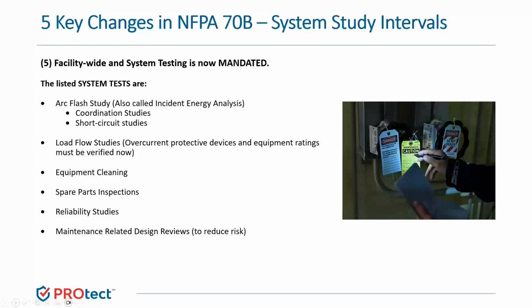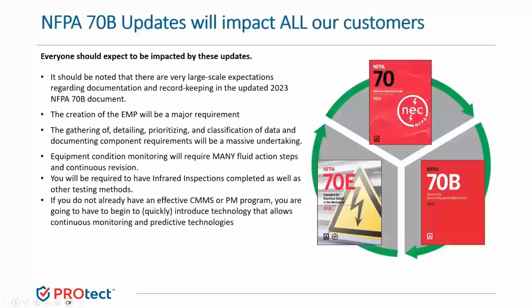A big key takeaway here is that if you already have an effective CMMS or preventive maintenance program, you should be able to build an electrical maintenance program that you can easily integrate with your existing mechanical integrity programs. You'll just need to pay close attention to manufacturer recommendations and defer to those NFPA guidelines on intervals or criticality for any items where you don't have specific details from the manufacturer, just to make sure those pieces don't get missed as you're building out this program.